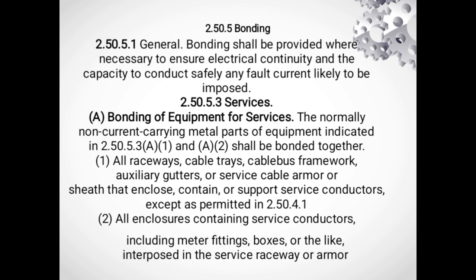2.50.5.3 Services. A. Bonding equipment for services. The normally non-current carrying metal parts equipment indicated in 2.50.5.3 A1 and A2 shall be bonded together. Number 1, all raceway, cable trays, cable bus, framework, auxiliary gutters, or service cable armor or sheath that enclose, contain, or support service conductor, except as permitted in 2.50.4.1. Number 2, all enclosure containing service conductor, including meter fittings, boxes, or the like interposed in the service raceway or armor.